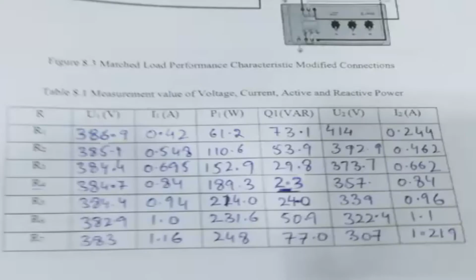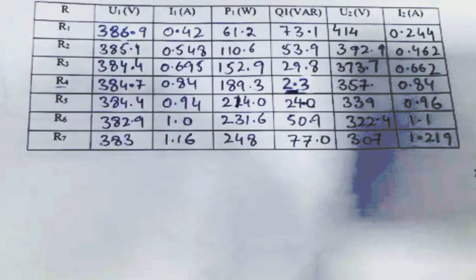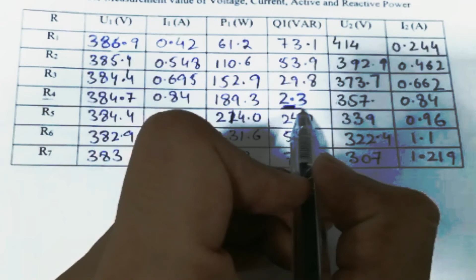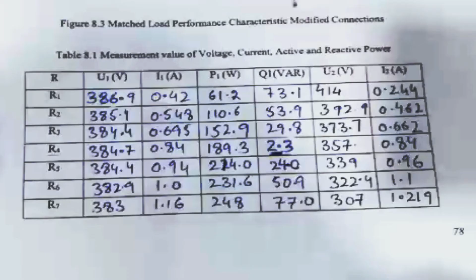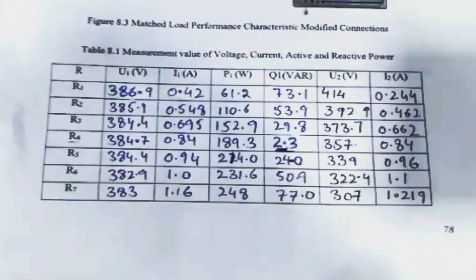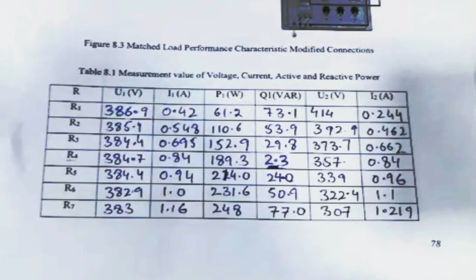Here we have noted down the values from R1 to R7, and you can see here that at R4 we have the minimum value of the reactive power. This means this is the resistive load at which the line no longer consumes any reactive power, that is, at which matching of the line is achieved.